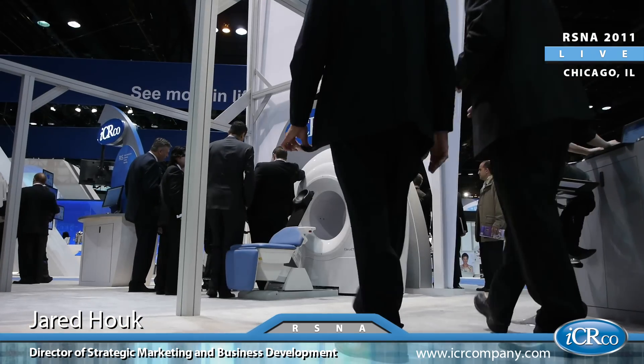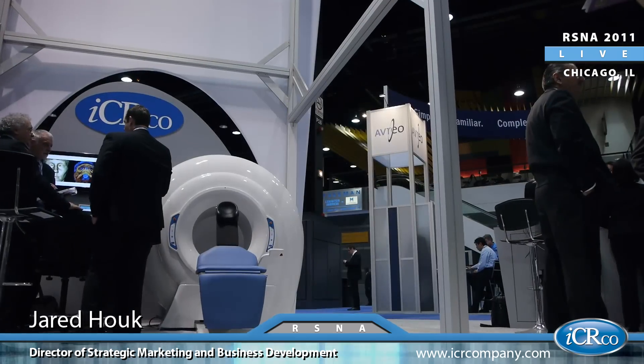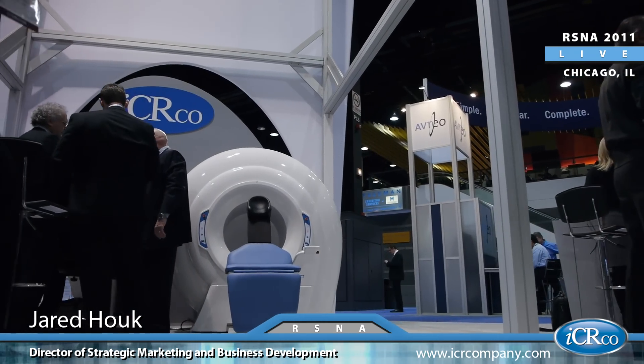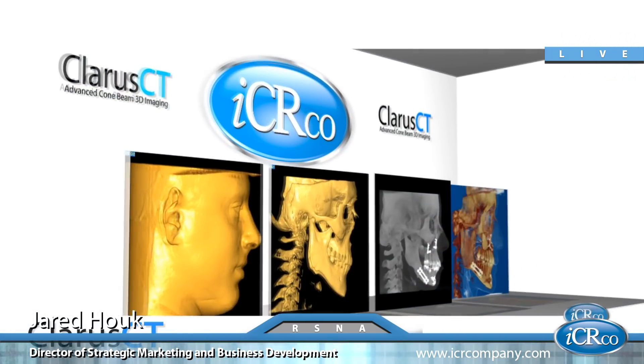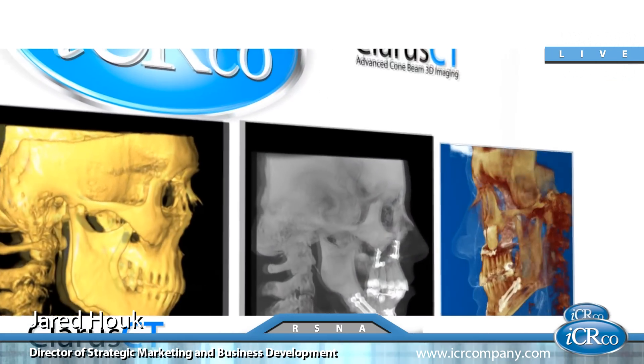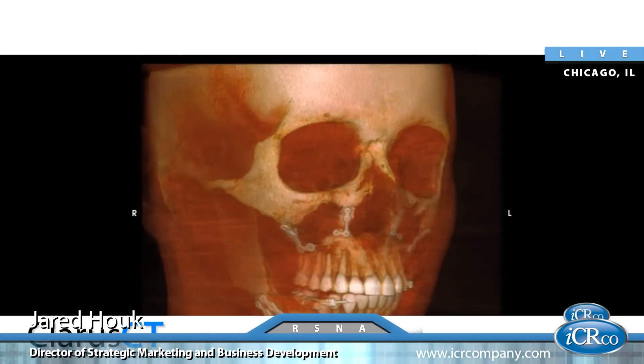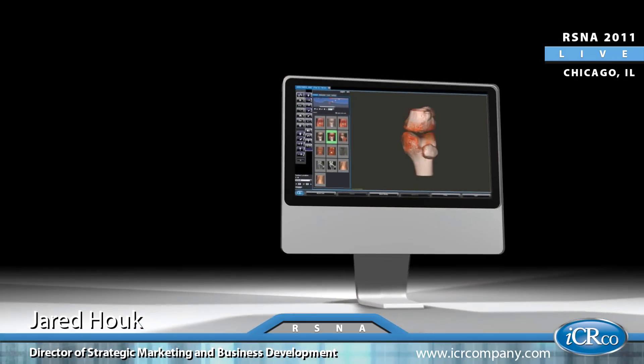The ClarusCT is a cone beam CT. Cone beam is a different technology for acquiring CT images. It actually uses a flat panel DR detector and takes 360 x-rays — 360 2D x-ray images — presents them in a 2D format, and then using software, we can reconstruct a 3D image.